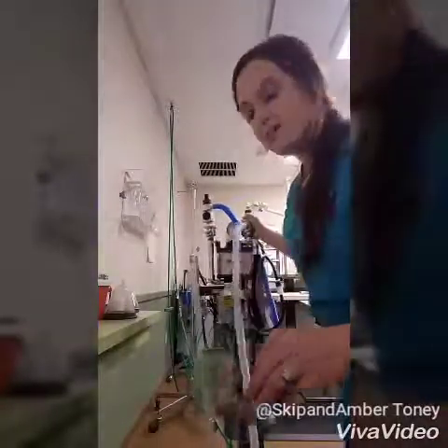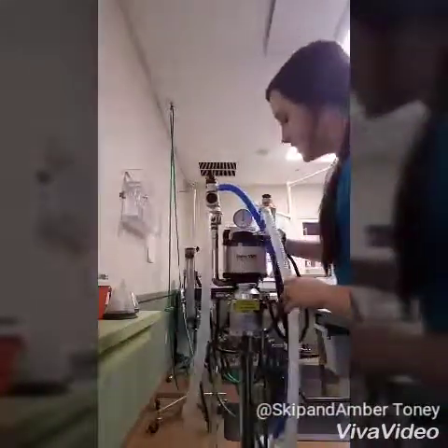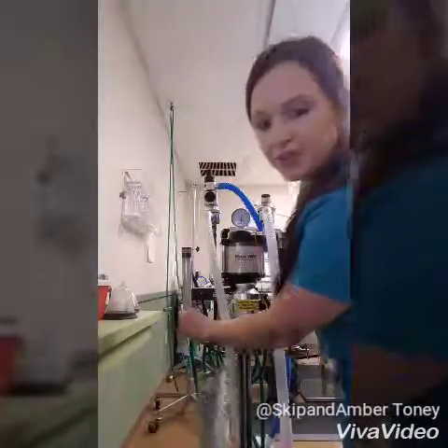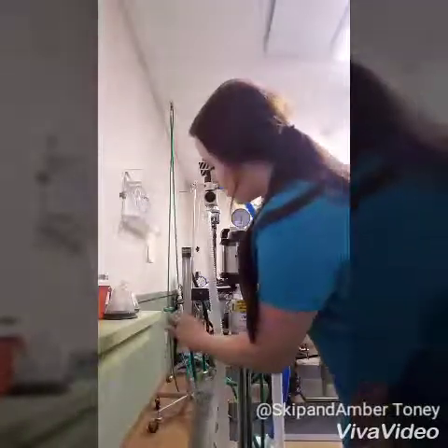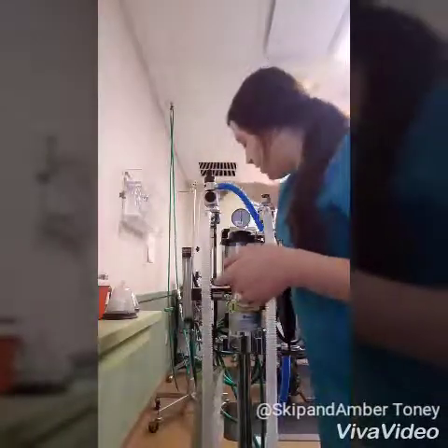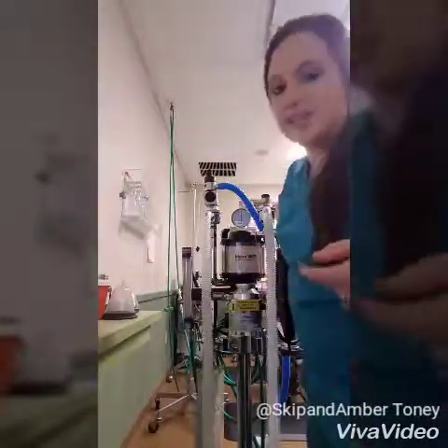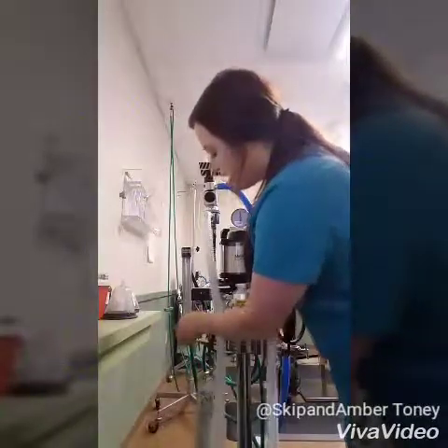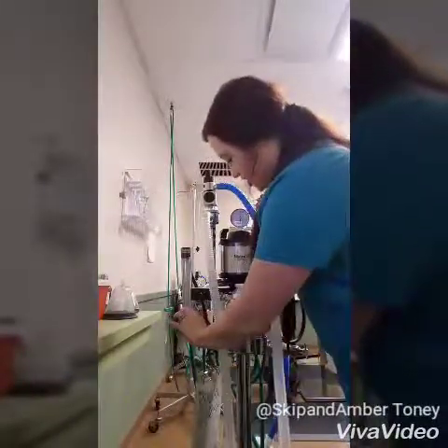I'm gonna pause this. Okay, I think you can see me pretty good. So I'm going to show you the parts of our anesthesia machine. This is our oxygen flow meter. All we have to do here is turn the little knob. We have oxygen up in our attic, like a very large oxygen tank, and we rarely have to refill it. So we have hoses that come down from the ceiling, as you can see there, and they're connected to both of our anesthesia machines. We have 2 anesthesia machines here in surgery. So all we would have to do is spin this little dial, and it would turn on our oxygen.